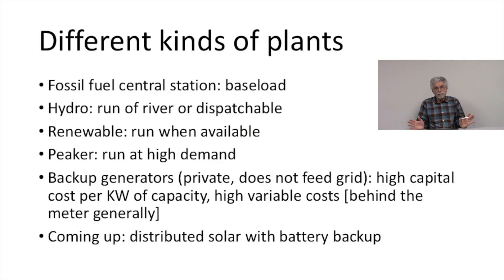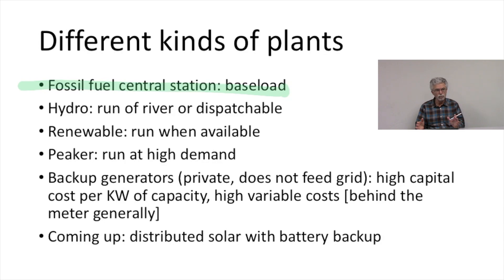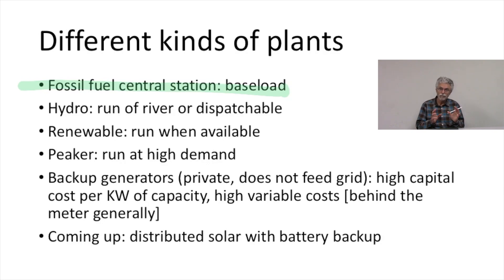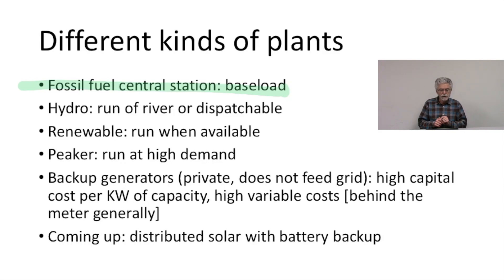There's the classic fossil fuel central station baseload power plant — a big new coal-fired power plant or a big new natural gas combined cycle unit. These plants are generally used for baseload capacity. Coal-fired plants are not designed to ramp up and down repeatedly, so we'll tend to want to run them as baseload. Natural gas plants can ramp a little faster and follow loads a little better, so depending on whether we want a plant to run steady all the time or to ramp, we might consider a different mix of coal and natural gas.